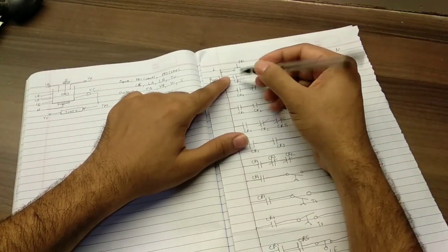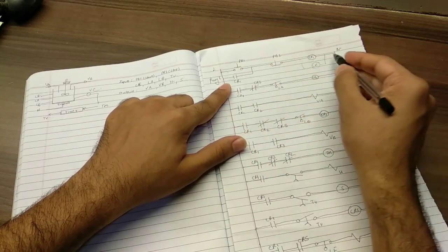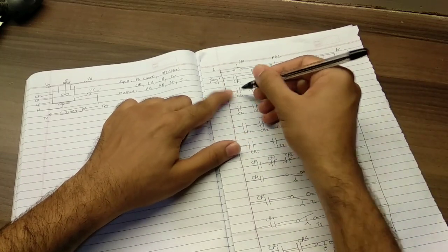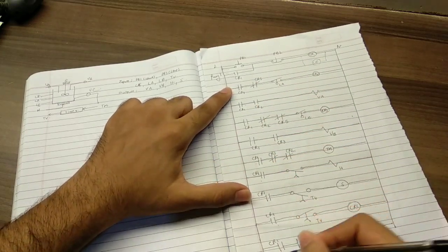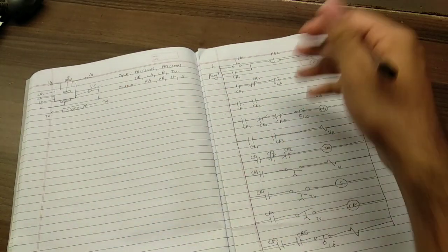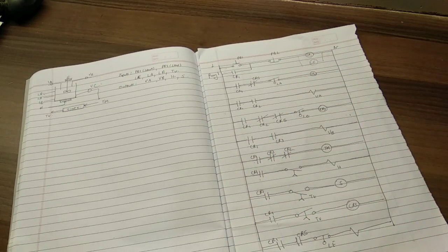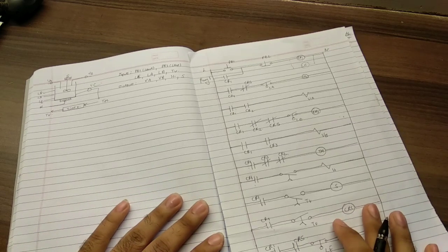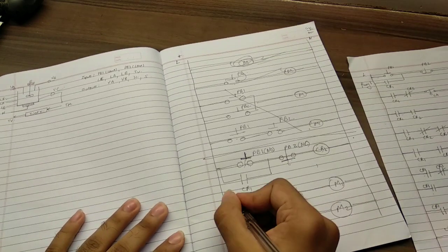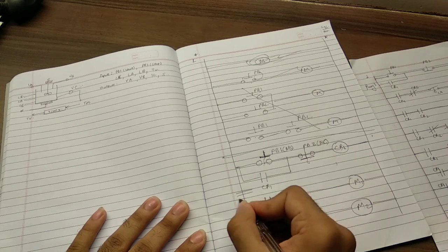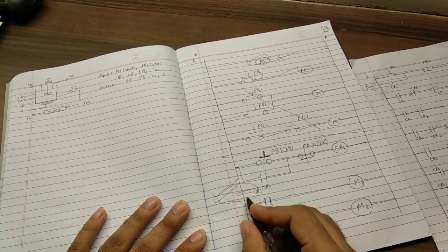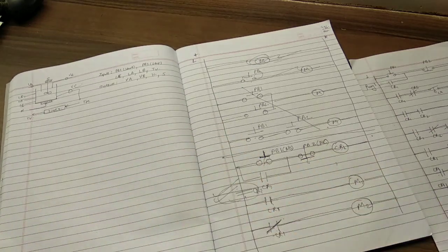Okay, so this is similar latch operation, and observe that every rung has a CR1 in the beginning. That means any rung cannot be actuated without the permission of CR1. So CR1 is like the boss of our programming right now. There's a common practice wherein you can add a CR1 over here too, and this is completely correct, so that all the rest of the rungs are dependent on CR1's actuation.